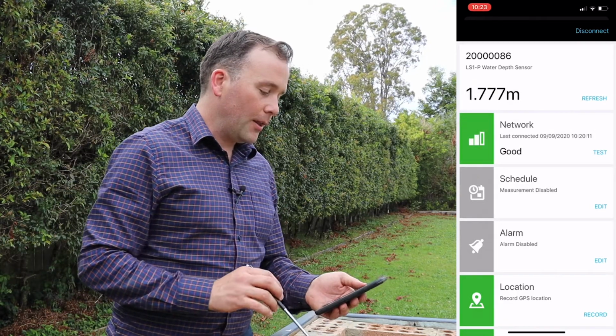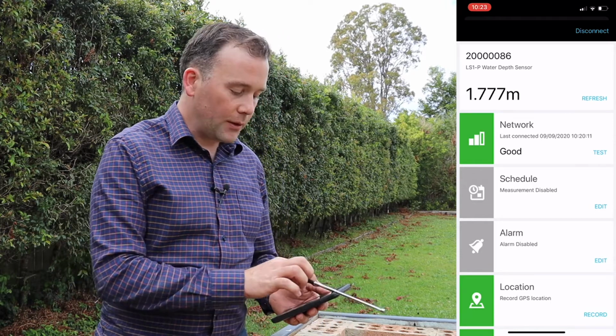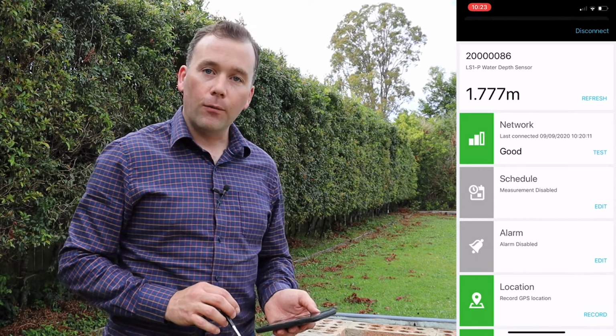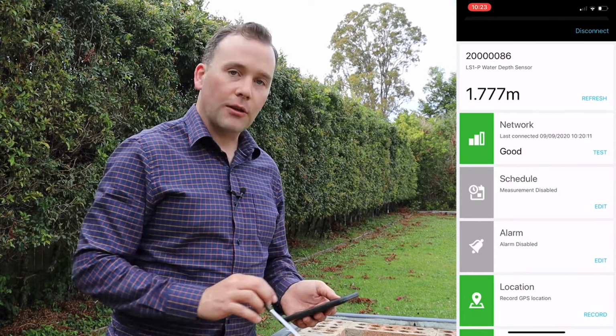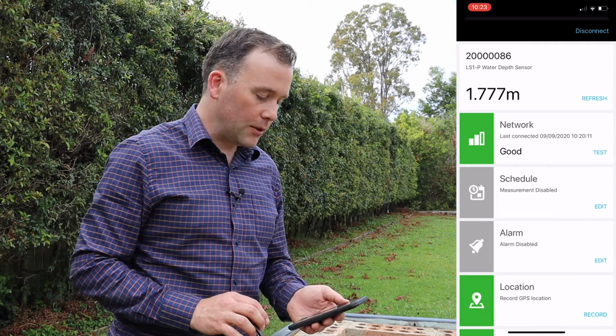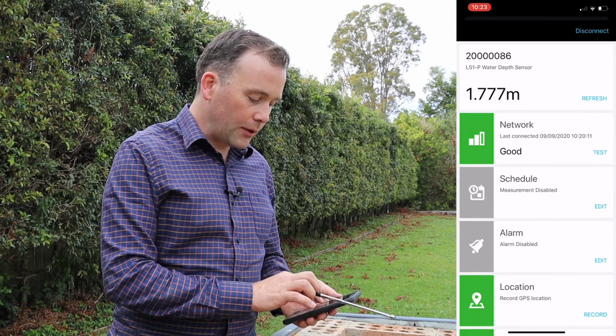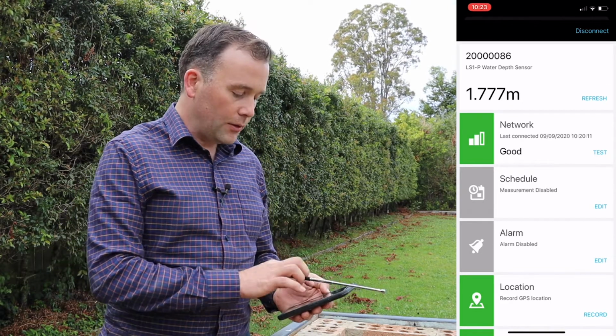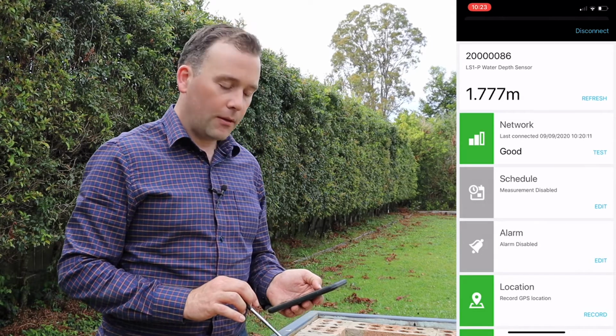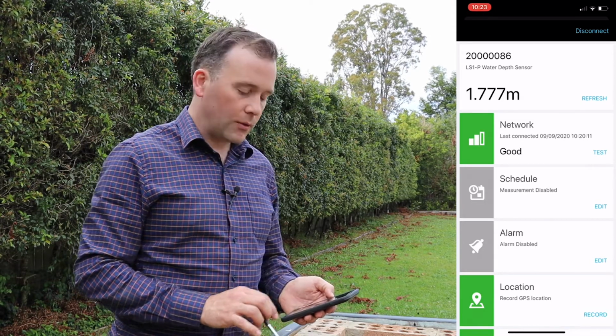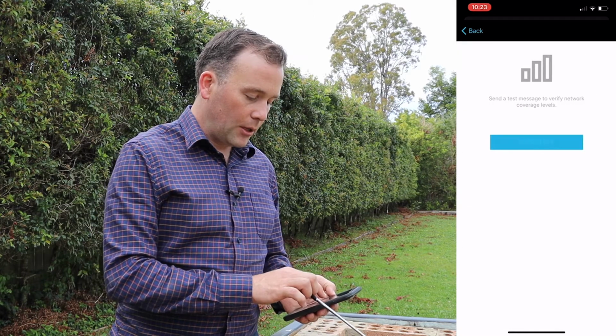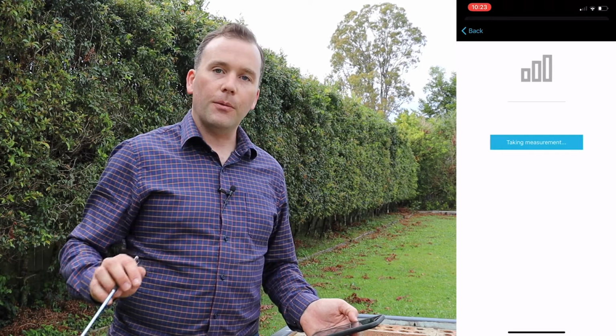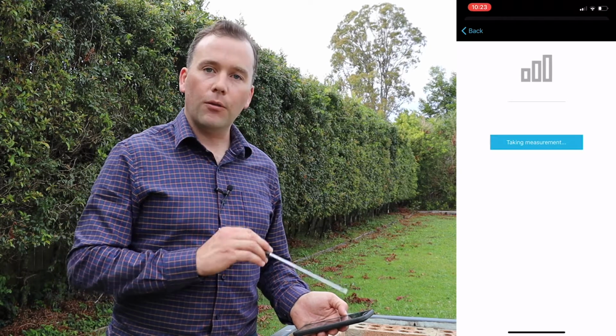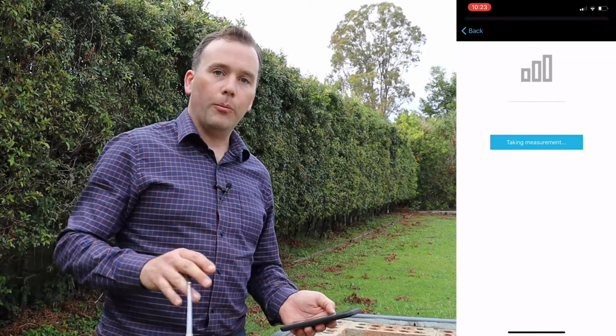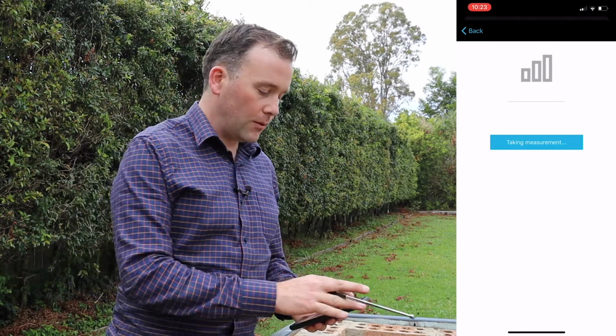So you can see it's loaded up, that's taken a reading off the device, and it's measured 1.78 meters of water above the sensor. So that is telling you how much water is above that pressure sensor. It's also telling us that we've got a good network connection from here, so you can run a test on that and it'll actually send a message and see what your signal strength is. So if I go into network and hit start test, then that sends a message up to the server. We can come back, it'll read it again in 30 seconds and it'll tell us what our signal strength is like at this location. Up on the portal you can see the exact received signal strength level.